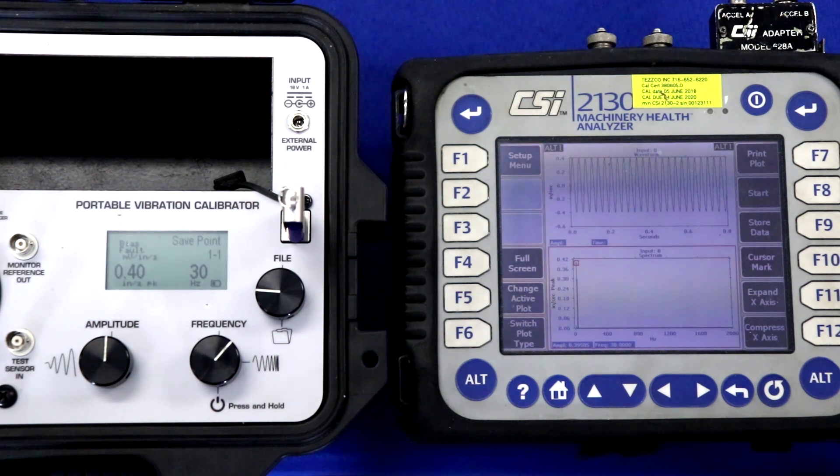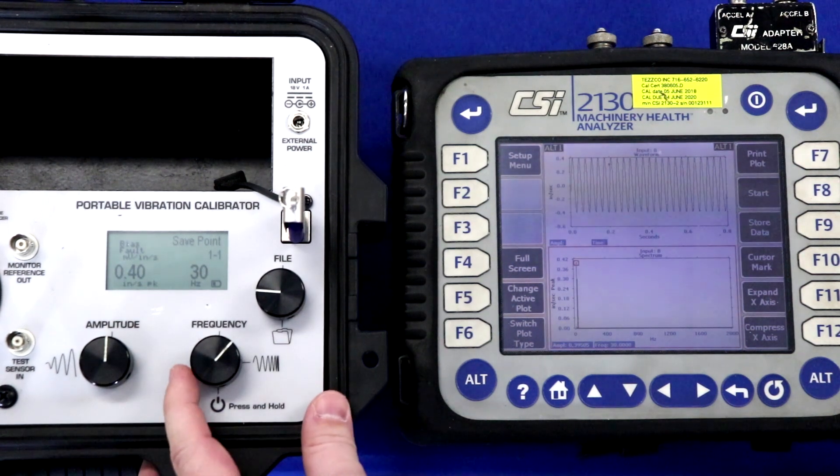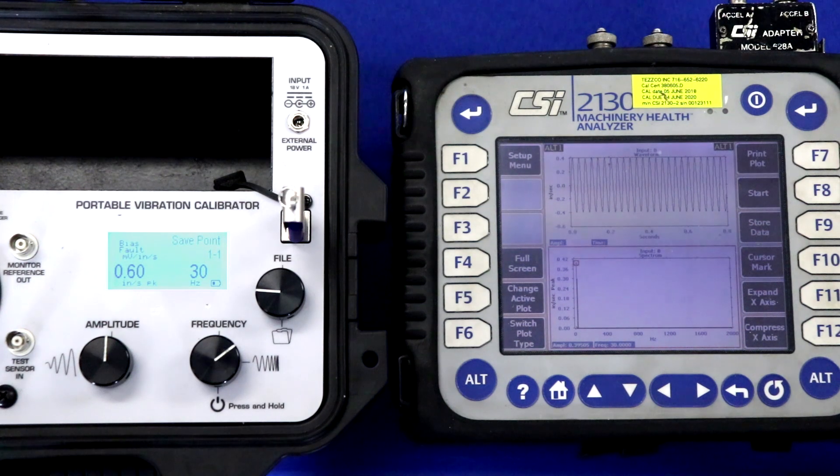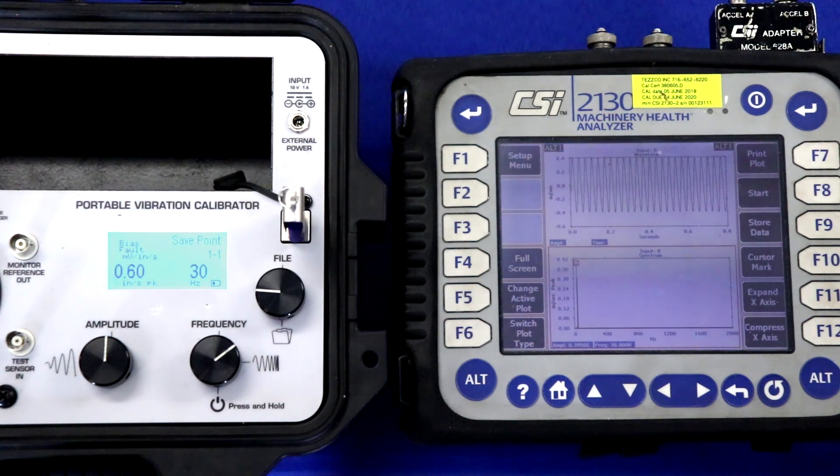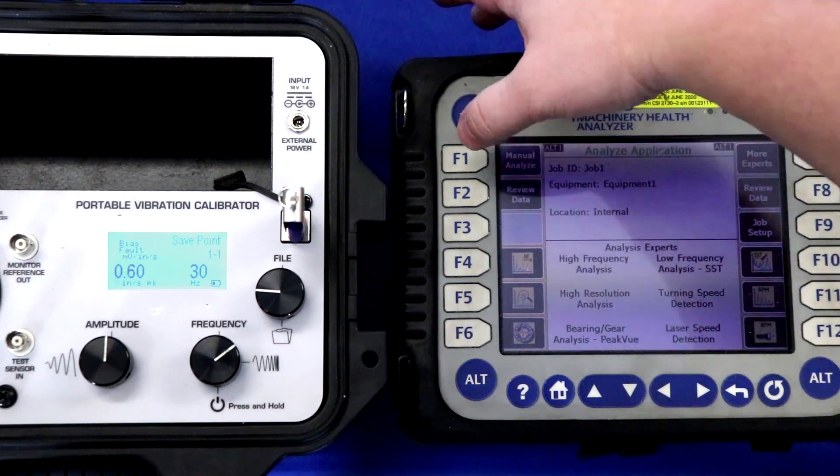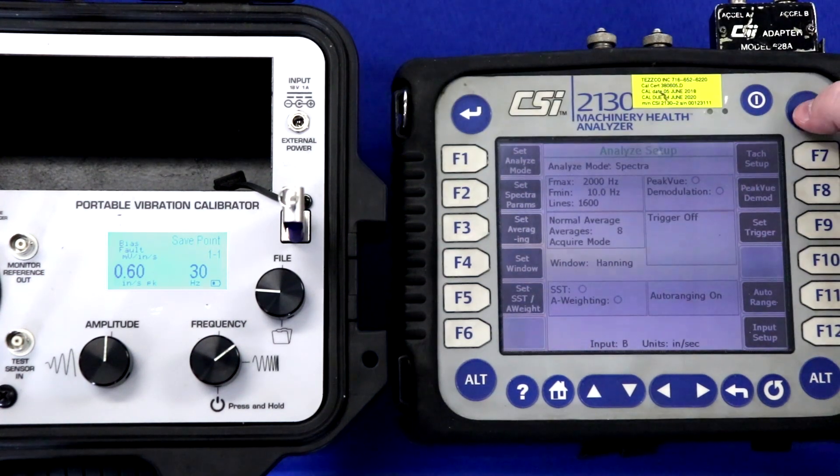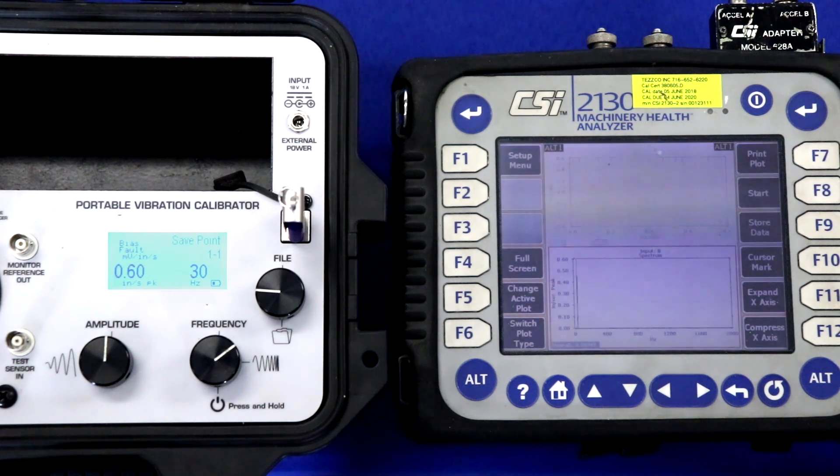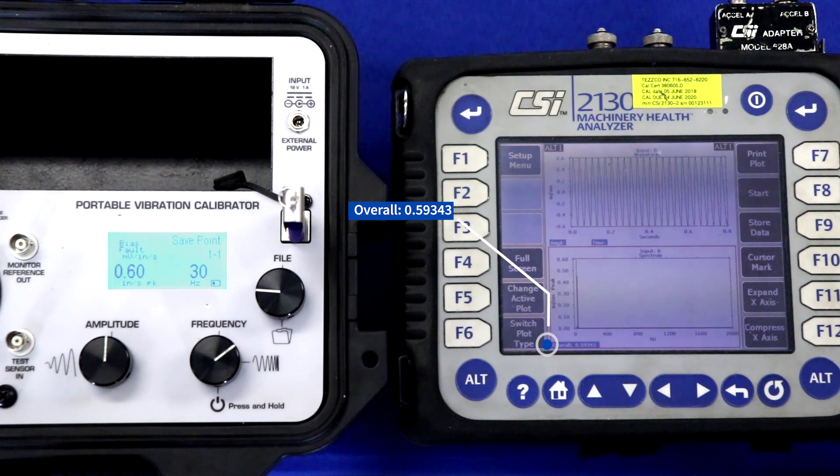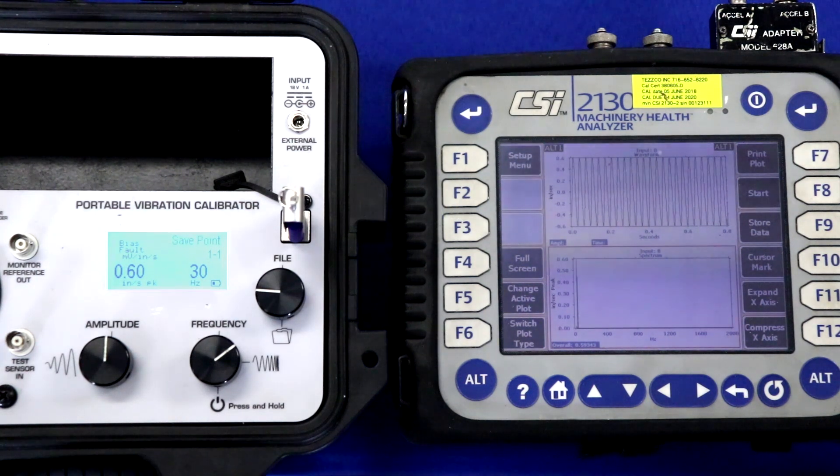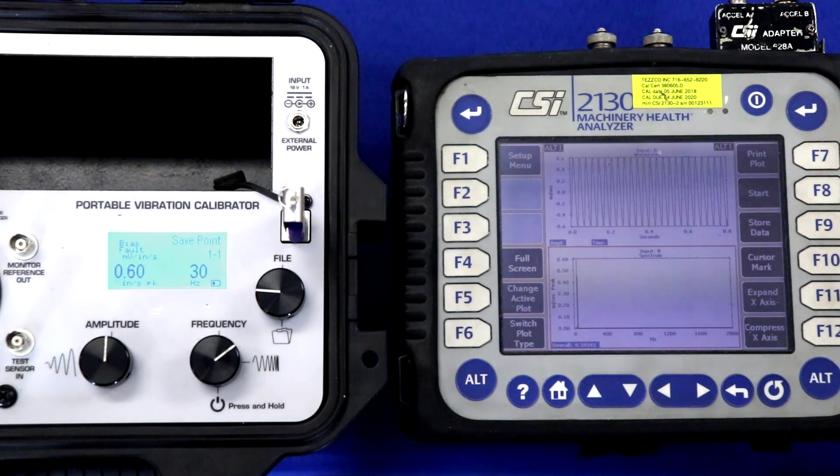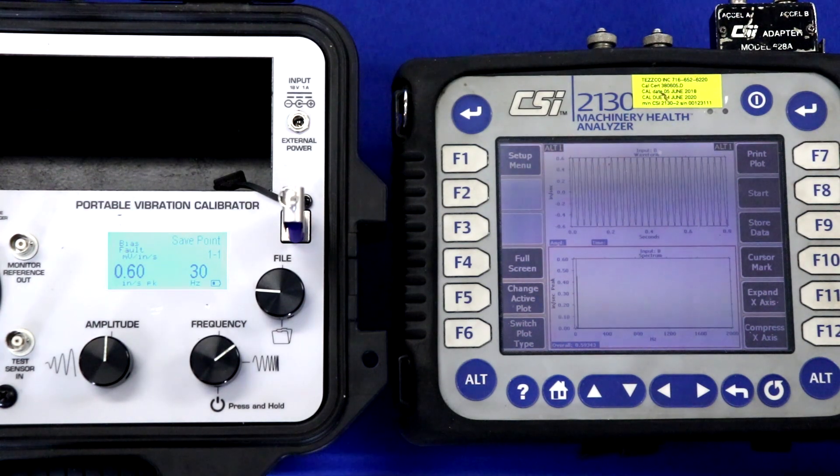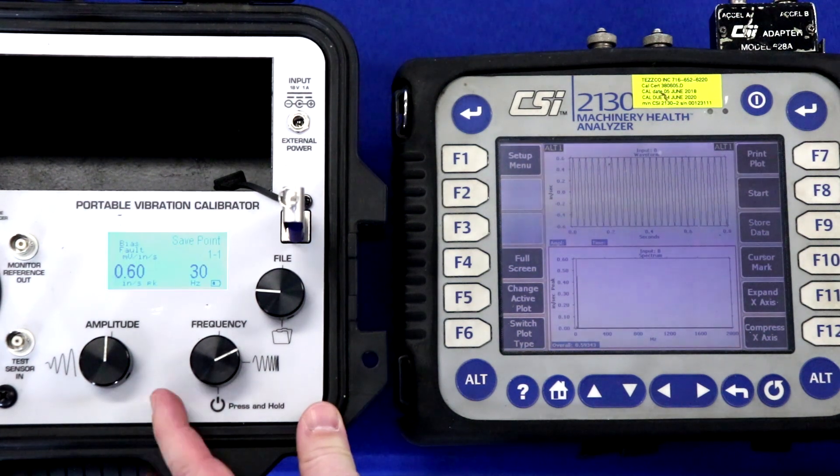Even though our sensor is magnetically mounted to the shaker, our vibration is centered upon the frequency of interest of 30 hertz. Let's check 0.6 inches per second peak, which is our known NIST traceable value from the shaker. We'll acquire data once more, and for the interest of brevity here, I'm not going to scroll the cursor over, but you can see that our overall vibration is 0.593, and our known vibration on the screen of the shaker itself is 0.6 inches per second peak, and once again, the vibration is centered at 30 hertz.